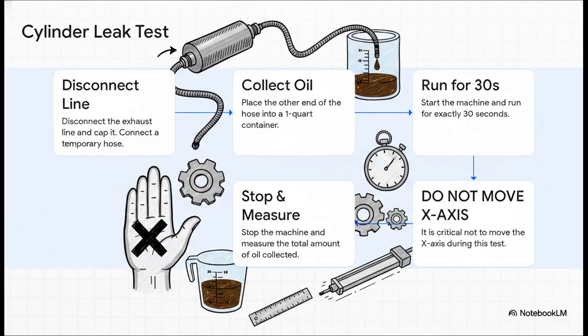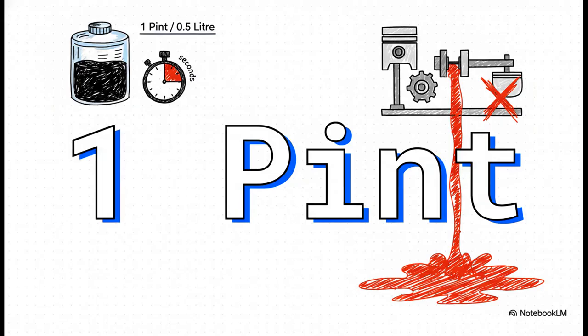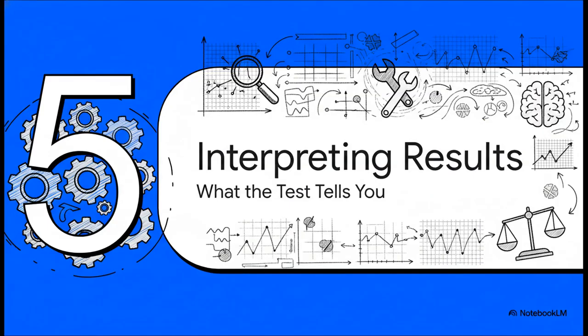After 30 seconds on the dot, stop the machine and measure whatever oil you've collected. And here we are, our second magic number for today. The absolute maximum amount of oil you should see in that container after 30 seconds is 1 pint, or about half a liter. If you've got more than that, well, that's telling us we have a problem. All right, we've done the tests, we've gathered our data. Now for the moment of truth, the final and most important section, making sense of what we just found.